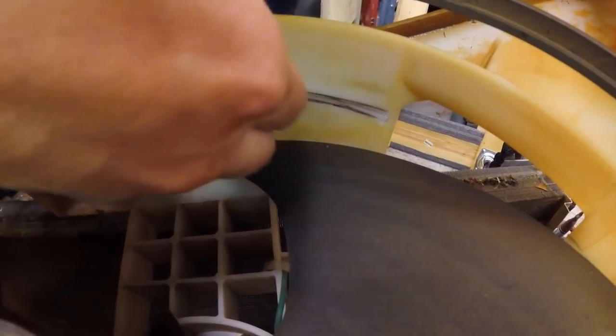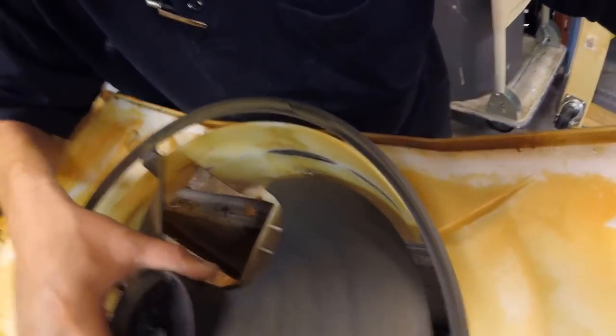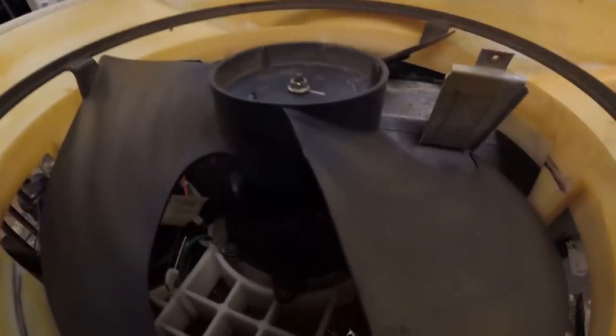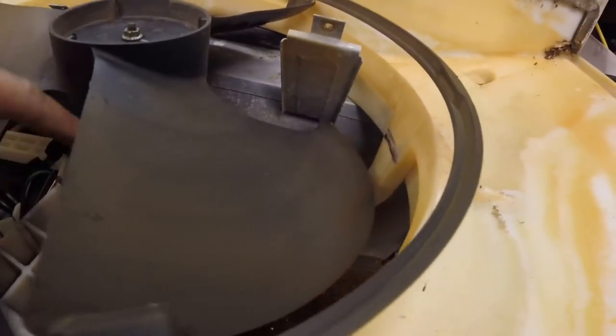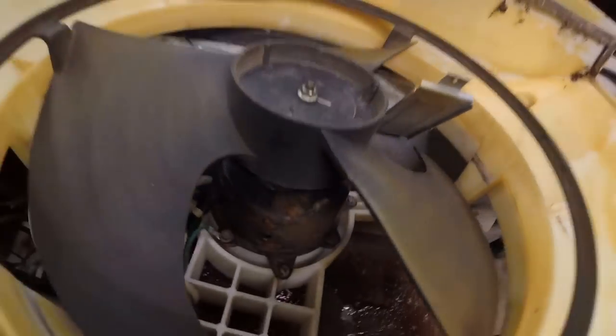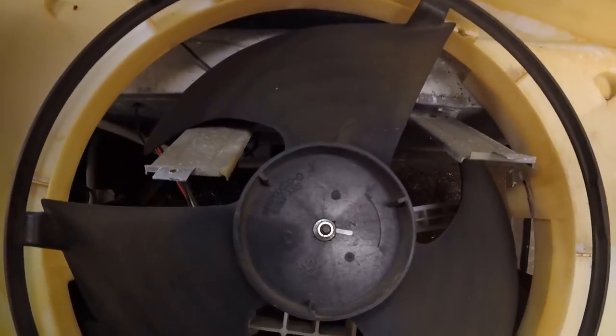out of this thing right here. Wap, wap, wap, wap, wap, wap, wap. This has been hitting it. So let's just change the fan blade, see if that helped. And we'll check this motor too, make sure it's fastened to the fan shroud properly.